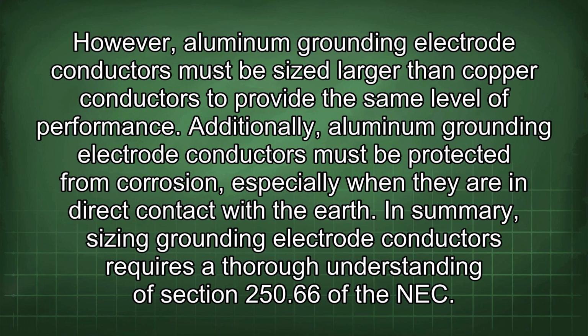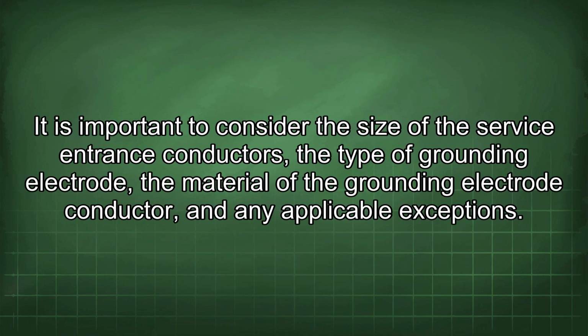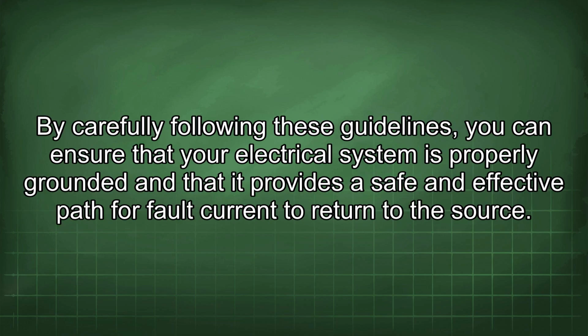In summary, sizing grounding electrode conductors requires a thorough understanding of Section 250.66 of the NEC. It is important to consider the size of the service entrance conductors, the type of grounding electrode, the material of the grounding electrode conductor, and any applicable exceptions. By carefully following these guidelines, you can ensure that your electrical system is properly grounded and that it provides a safe and effective path for fault current to return to the source.